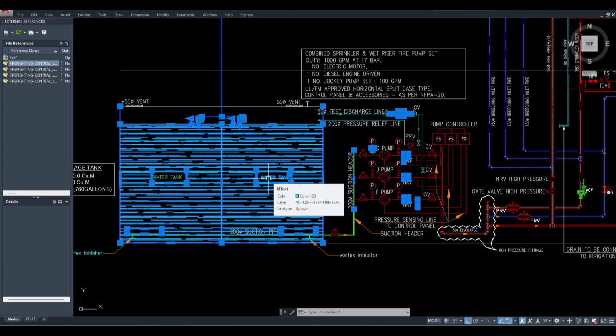But the fire tank should be in proximity to the fire pump room. It should not be more than 15 meters away from the fire pumps. So of course, you cannot keep it on the roof.